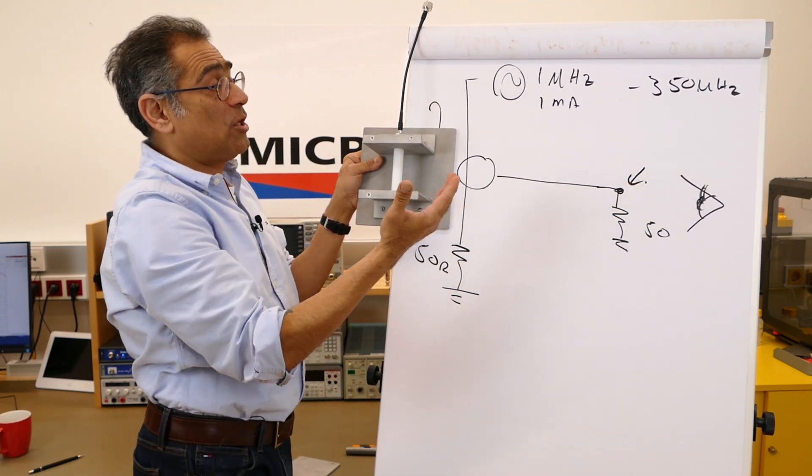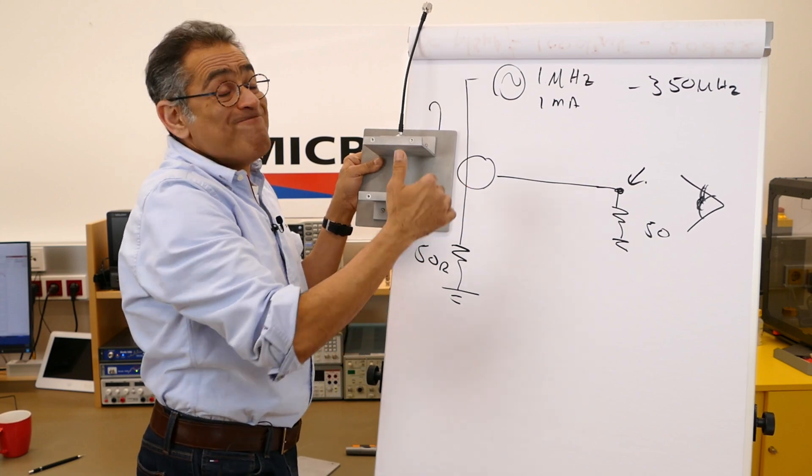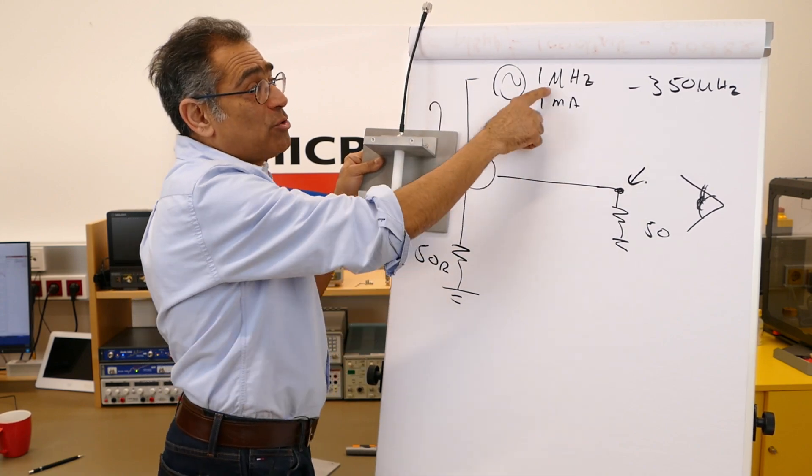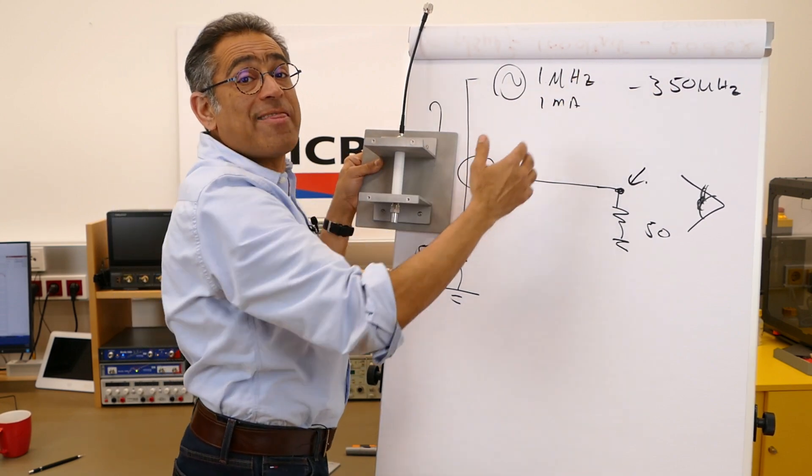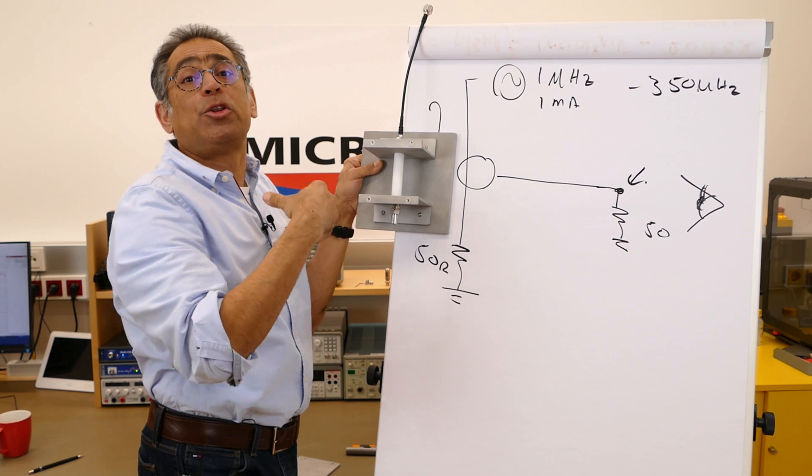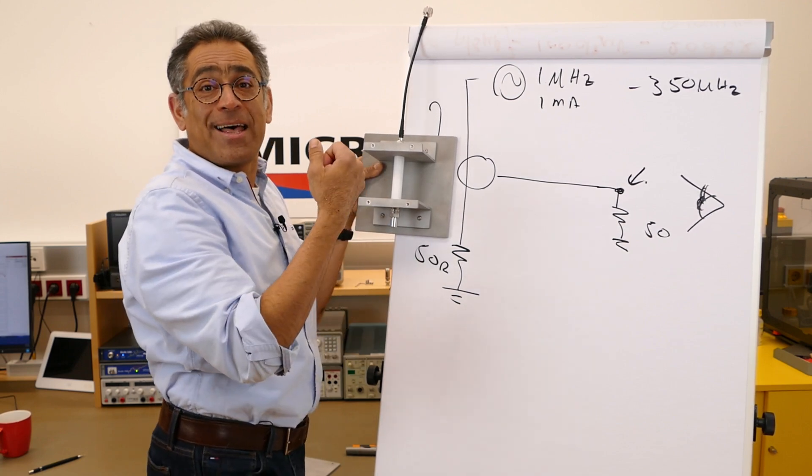Another issue that we have is that because the frequencies are very high, things change - the amplitude that you're injecting at one megahertz may not be the same as the one that you expect at 350, and therefore we have to calibrate and normalize everything before we can make a correct measurement.